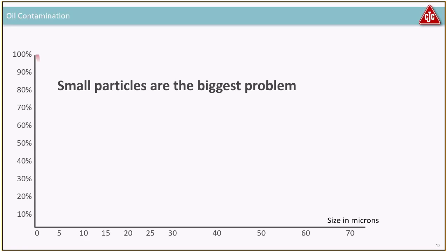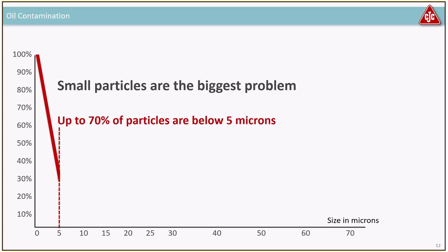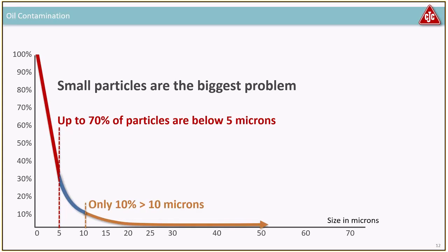There are a lot of these small particles — roughly 70% of them are below 5 microns. About 90% of particles found in an oil system will be smaller than 10 microns. This is because a bigger particle, like a 40-micron dust speck entering a gearbox or roller bearing and being crushed, will generate thousands of 1, 5, or 10 micron particles. The bigger particles are also much easier to filter out with a standard inline filter, so you always have far more of the small ones.